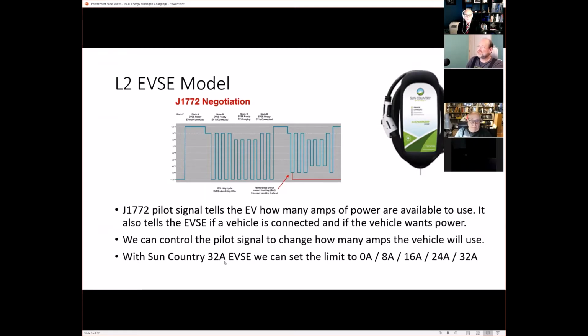So with the Sun Country chargers that we use mostly, they're all like the standard 40 amp EVSE, which can offer up to 32 amps of power. And we can set it to offer no power, 8 amps, 16 amps, 24 amps, or 32 amps. So basically in 25% increments of its maximum power. And they have chargers up to 80 amps, and they are proportionate. So they would do 25, 50, 75, and 100% of that power.